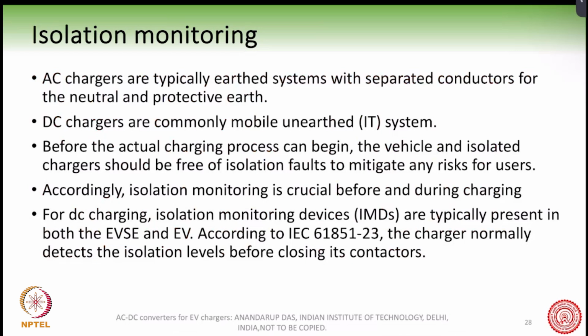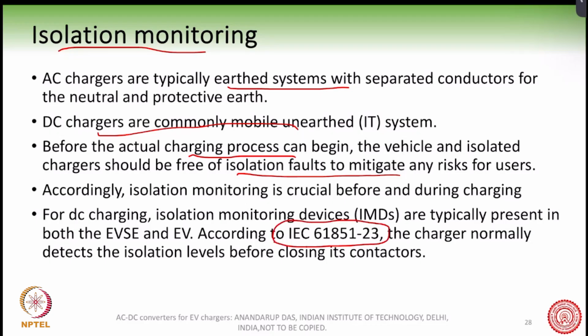And apart from this, we also should have isolation monitoring, because as I told you, AC and DC, the safety of the personnel is very important. So DC chargers are mobile unearthed IT systems. And AC chargers are typically earthed systems. So this is a difference between these AC and DC chargers. But before the actual charging process can begin, the vehicle and charger actually communicate and say that there is no isolation fault and the charging can safely begin. So there are these standards which one must keep in mind, which the charger will normally detect, the isolation levels, before you can begin the charging process.